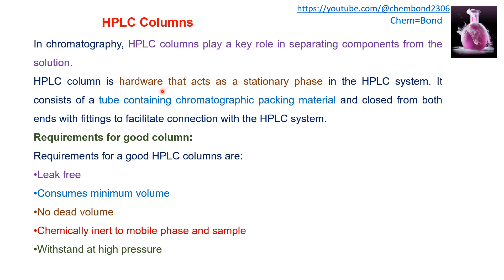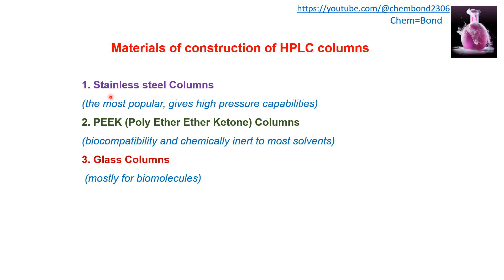The tube is made of plastic, glass, or steel, and is packed with packing material that acts as the stationary phase. Requirements for a good column include being leak-free, consuming minimum volume, having no void or dead volume, being chemically inert to mobile phase and sample, and being able to withstand high pressure. Materials used for HPLC columns are stainless steel, PEEK (polyether ether ketone), and glass.